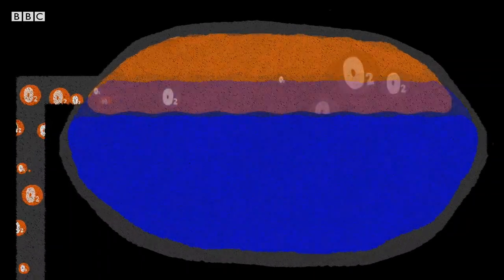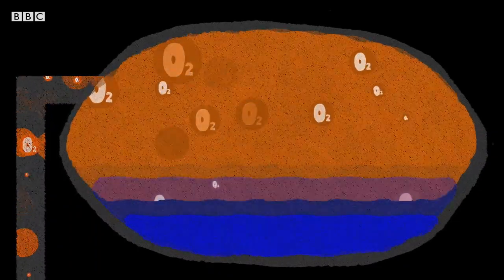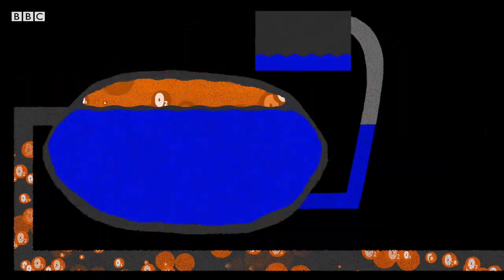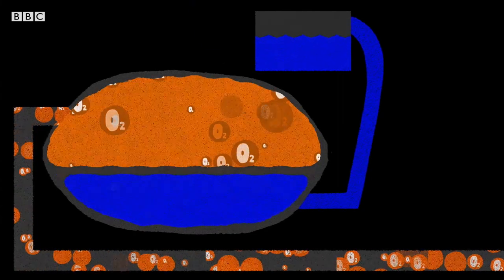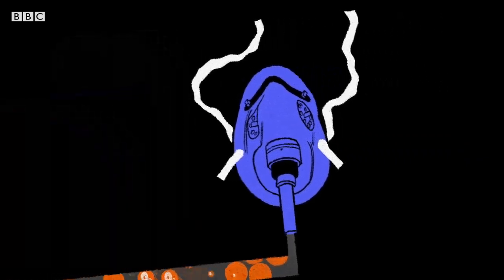It's a big bag with two flexible bladders inside — one for water and one for oxygen. The first bladder fills with oxygen and it pushes against the water bladder, so the water is forced through a tube into a tank above. If the power cuts out, the water in the tank flows down, pushing the oxygen out to the patients.